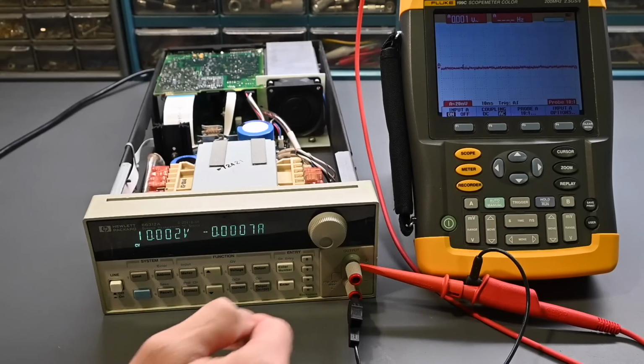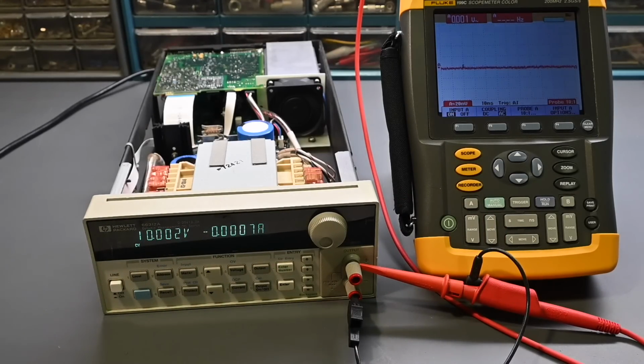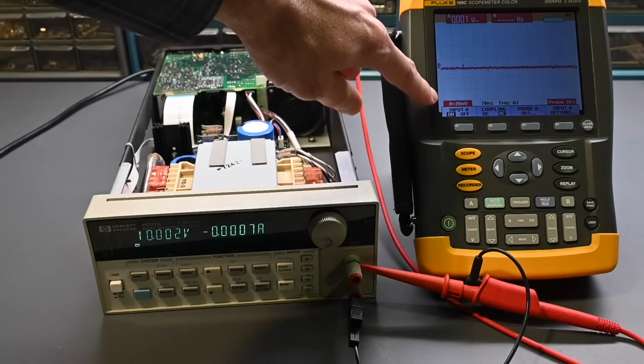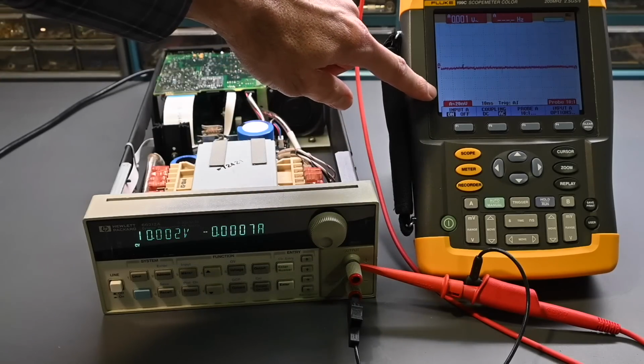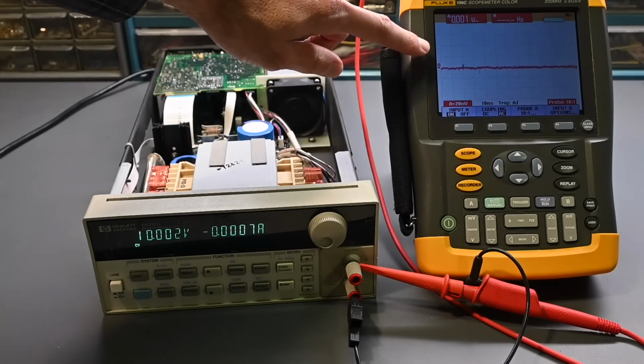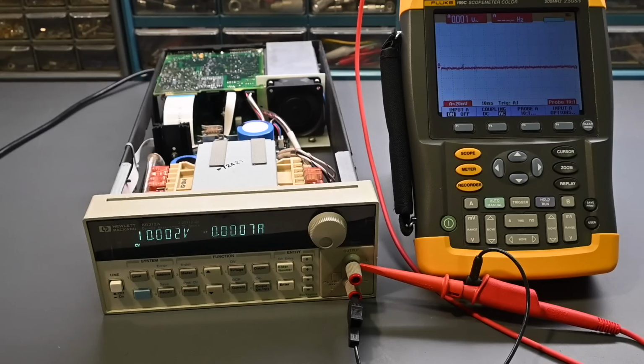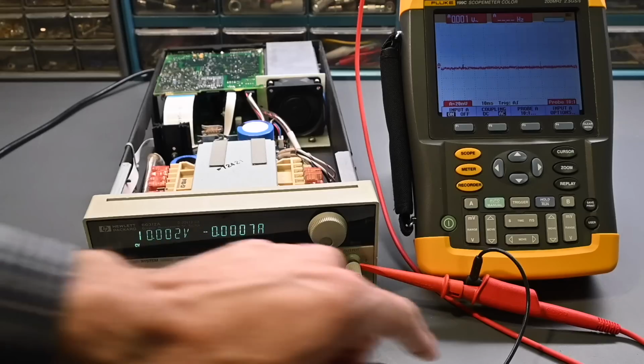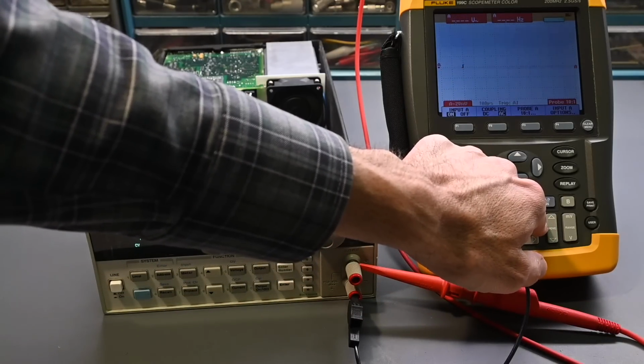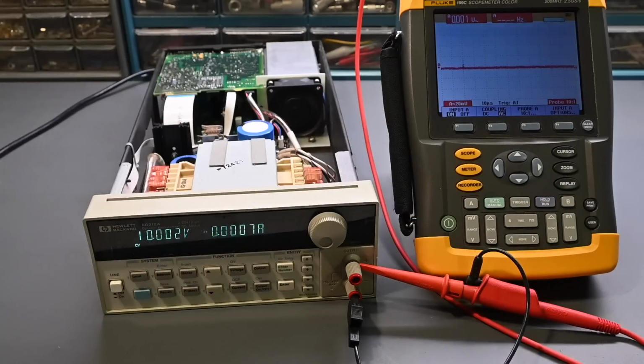If we go here, we're on AC coupling. Yes, we are. I have to reach around the camera a little bit here. So we're on AC coupling, and the input here is on 20 millivolts per division. There is absolutely no noise on the output. Very, very low. That looks outstanding. Compare that to the 100 kilohertz and all the crazy noise and spikes that we were seeing earlier, and all the oscillations that were going on. Looks like it's all taken care of. I'm very happy with this. If I speed the sweep time up just a little bit, just to double check, to a higher frequency, yeah, no problems. Looks really good.